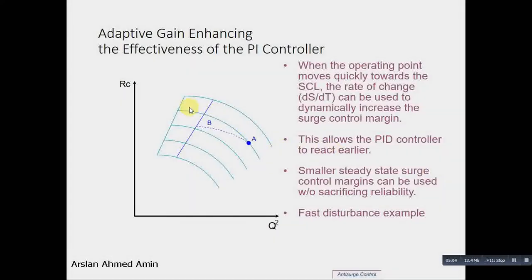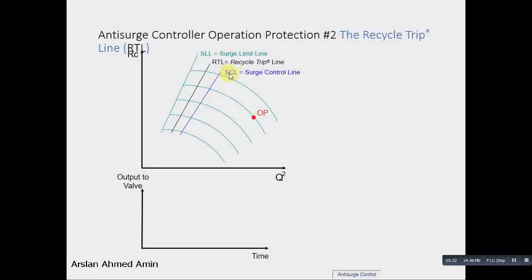If the surge point comes very fast to this point, we can use the rate of change, or derivative, this magnitude, and give this much higher response to the control valve, which is also known as the recycle trip response. This is the surge control line and this is the recycle trip line. This is for the derivative action. This is the proportional and integral action, and the recycle trip line is the derivative action.